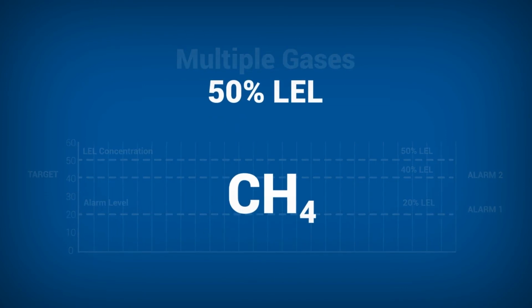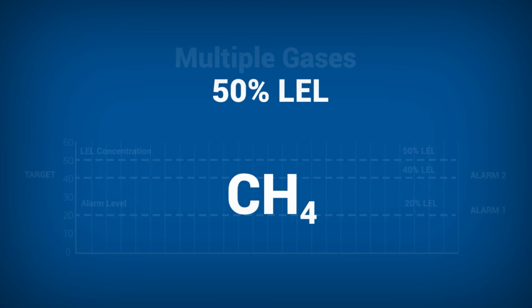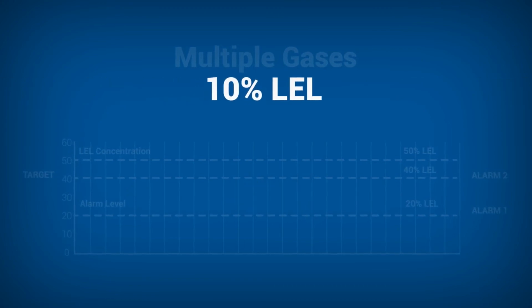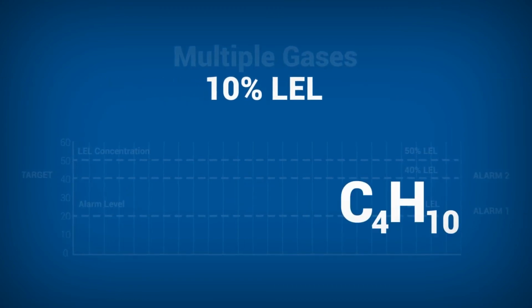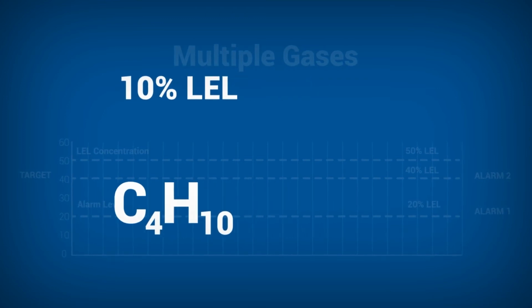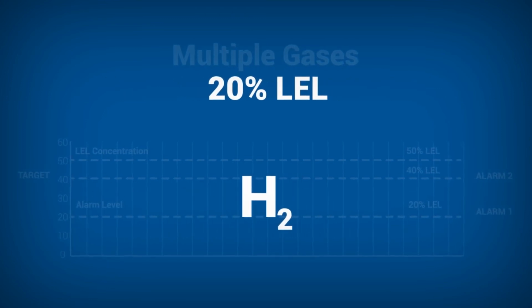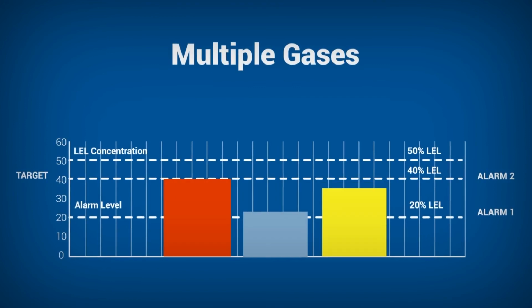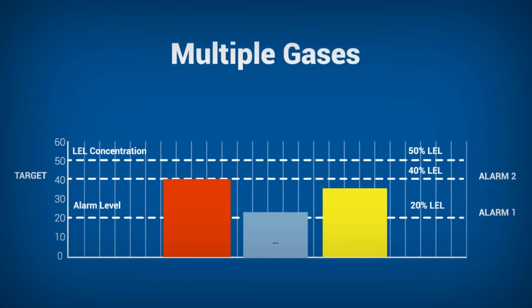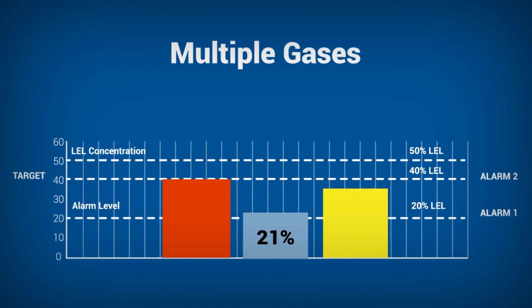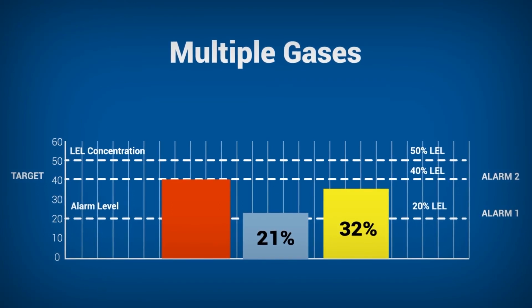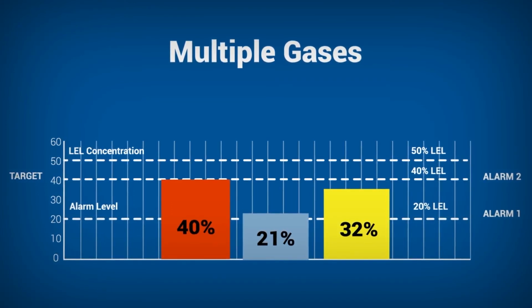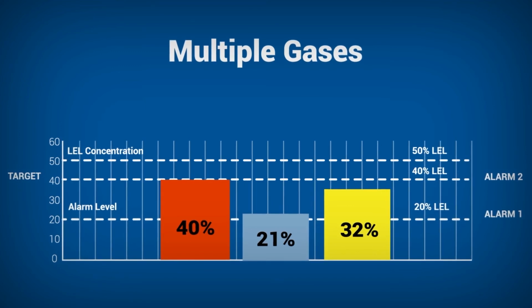For the final test, all sensors were calibrated to 50% LEL methane and exposed to an environment with 10% LEL methane, 10% LEL butane, and 20% LEL hydrogen. All sensors reported some level of gas, 21% by the NDIR, 32% by the Pellistor, and 40% by the MPS. Only the MPS reaches the important second alarm level, potentially saving lives.